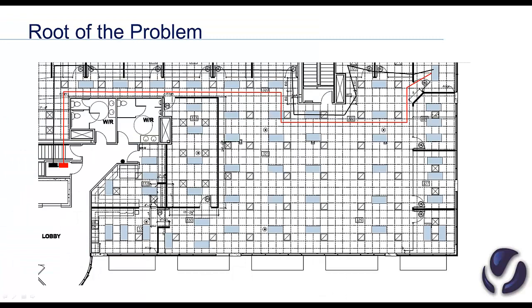If we wanted to install network lighting control, otherwise known as low voltage lighting, we would install a panel full of relays on the wall here. We would then have to pull an MC cable or install a conduit all the way across the floor, past the wall box location, straight to the fixture. This wire is the switch leg. Remember, the switching location used to be in the wall. It's not anymore. It's on a relay in this panel, so it needs a switch leg.